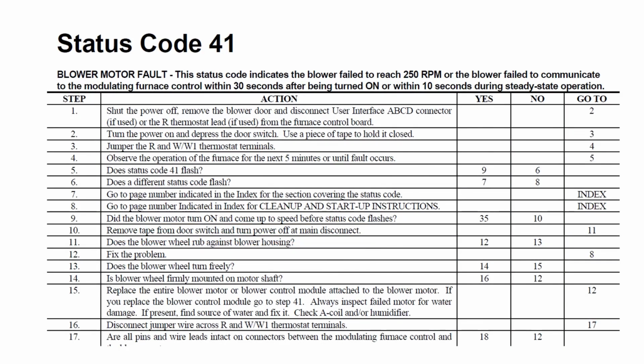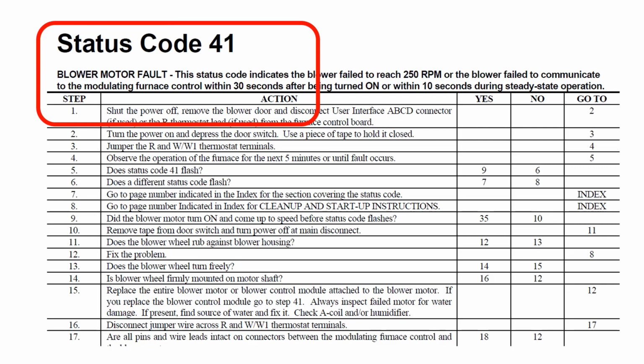Many manufacturers will have a troubleshooting guide for their ECM motors. In this case, a status code of 41 will tell you that the blower motor has faulted, and you will need to follow the troubleshooting procedure to find out what the problem is.